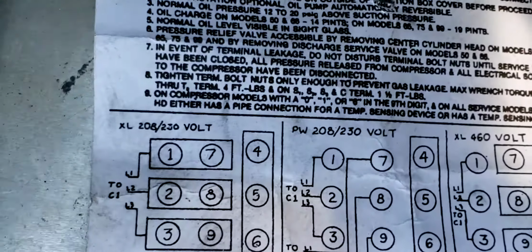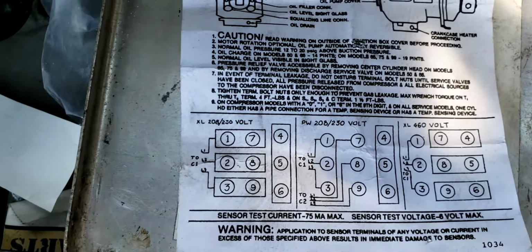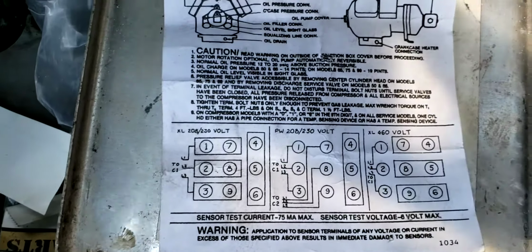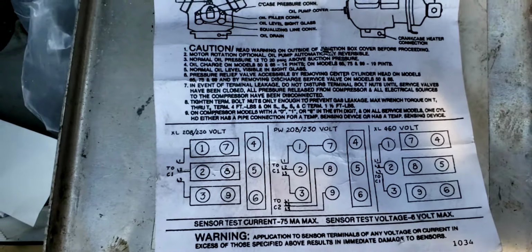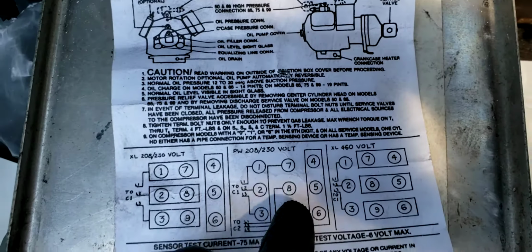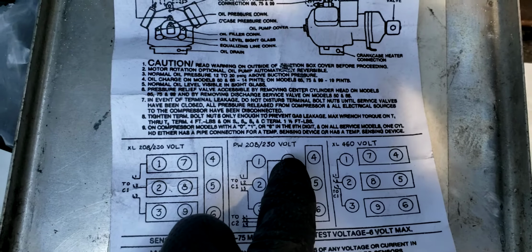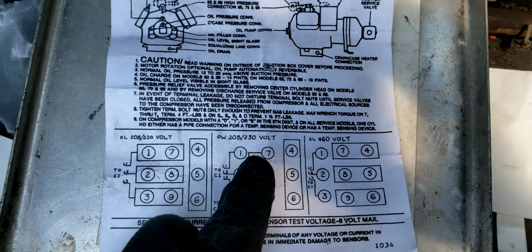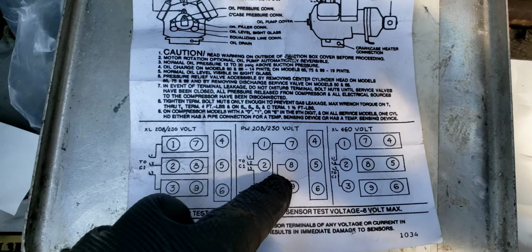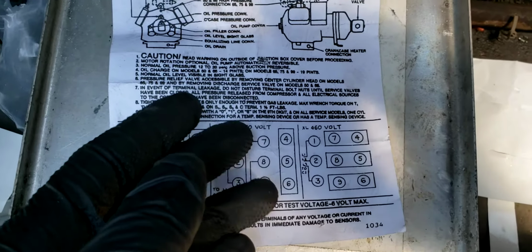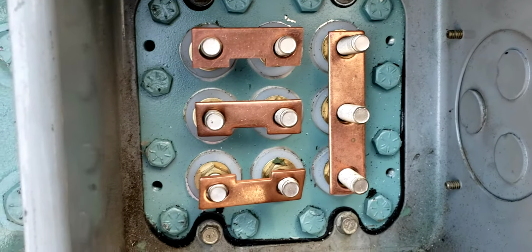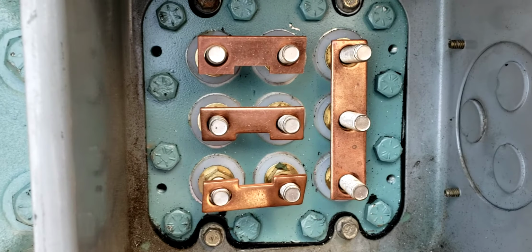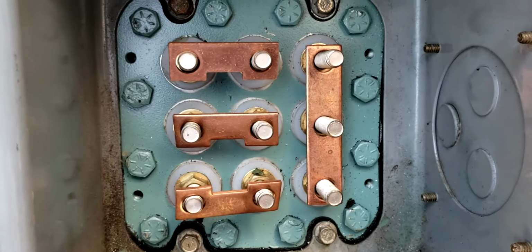You could put L3 up here if you want, or L3 in the middle. It doesn't really matter, because it's a reciprocating compressor. Rotation not sensitive, unless you're comparing rotation between the 2 windings inside, because there's two separate windings, hence the reason why you have the part winding option, hence the reason why you have all these terminals, because they want to give you the option for part winding. And so when you're doing the part winding option, both windings have to have the same rotation.